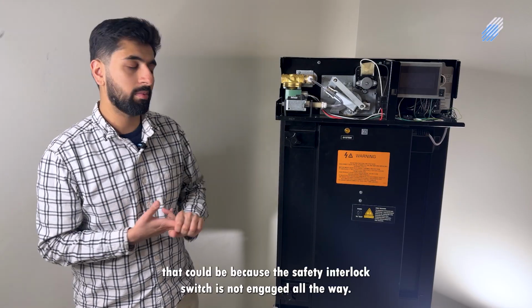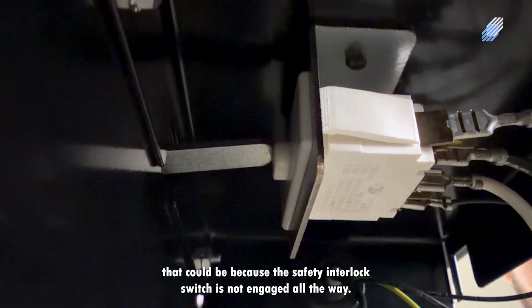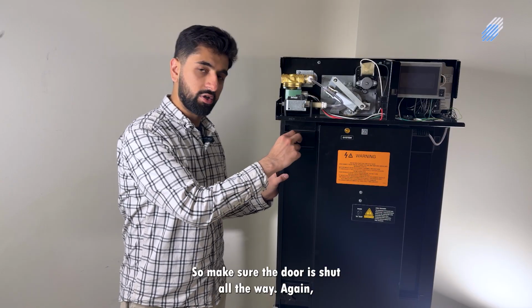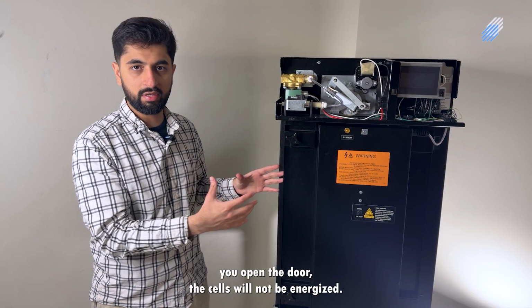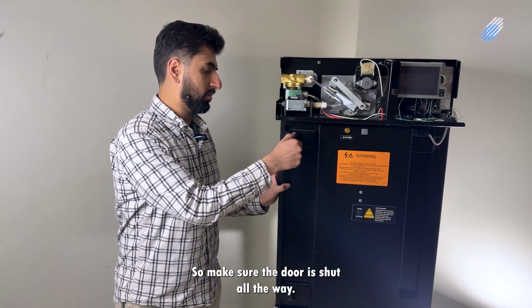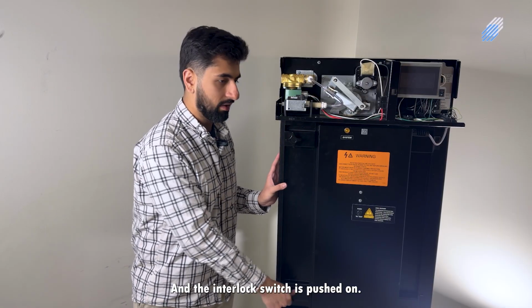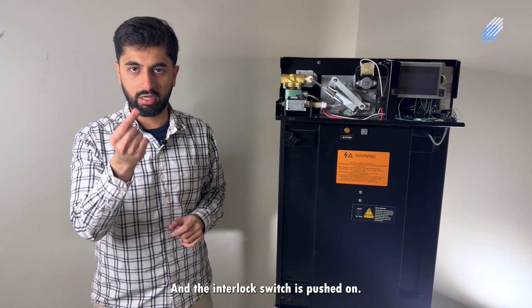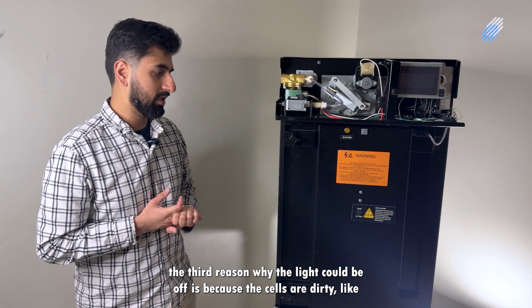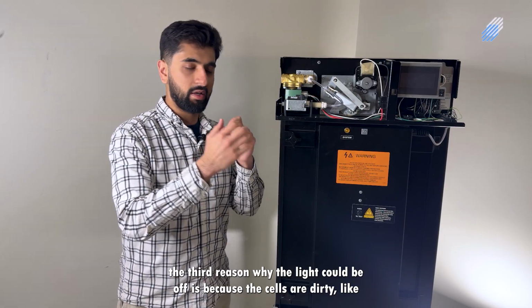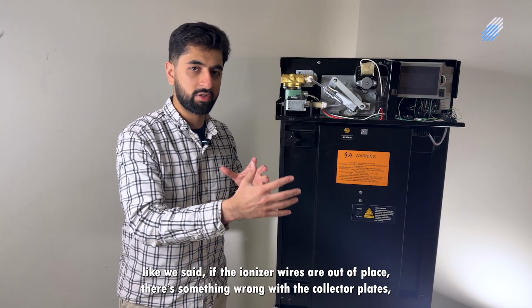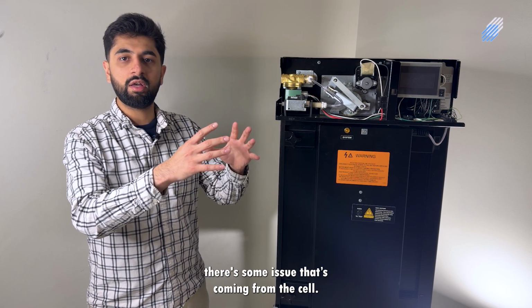Number two, that could be because the safety interlock switch is not engaged all the way. So make sure the door is shut all the way. Again, if you open the door, the cells will not be energized. So make sure the door is shut all the way and the interlock switch is pushed on. The third reason why the light could be off is because the cells are dirty. Like we said, the ionizer wires are out of place, or there's something wrong with the collector plates. There's some issue that's coming from the cell.